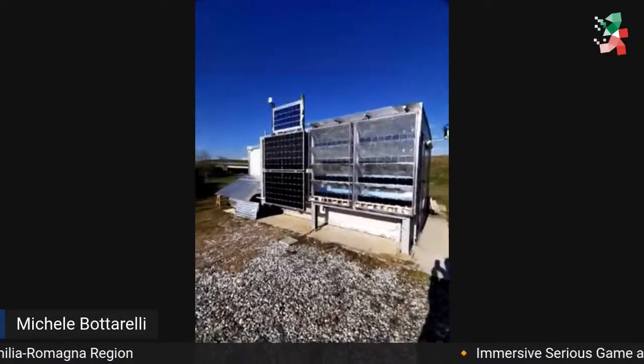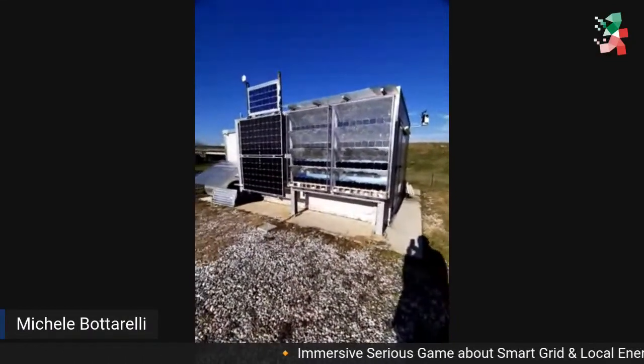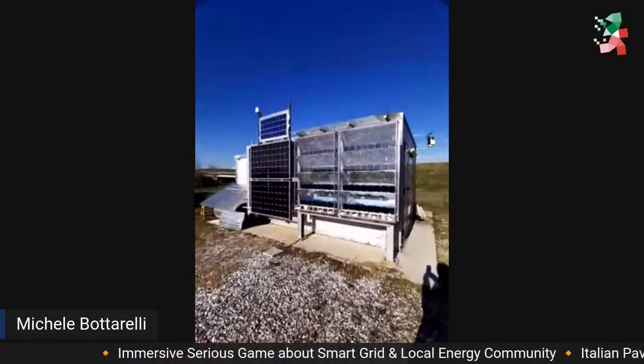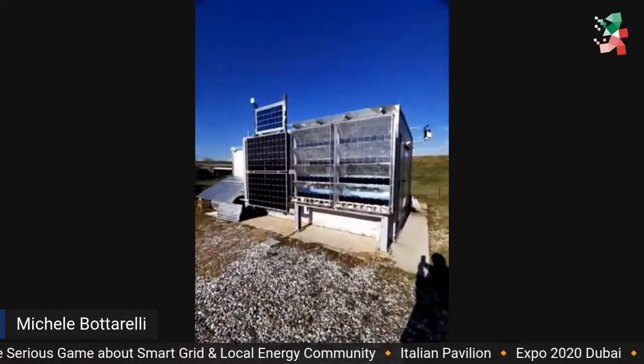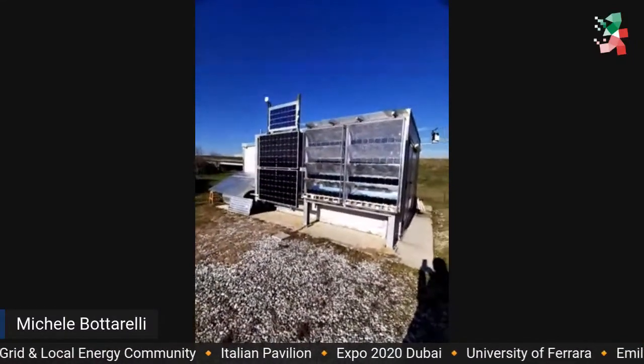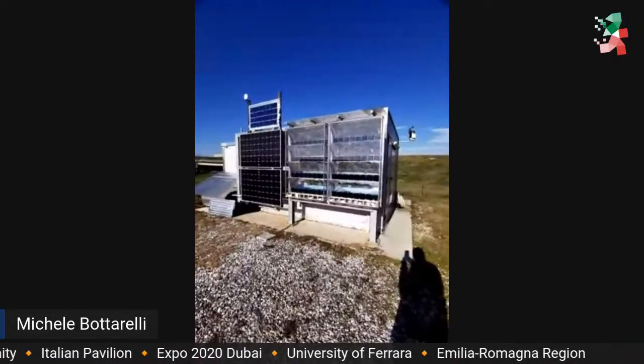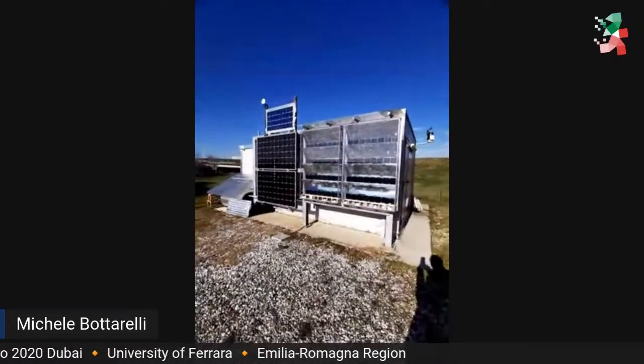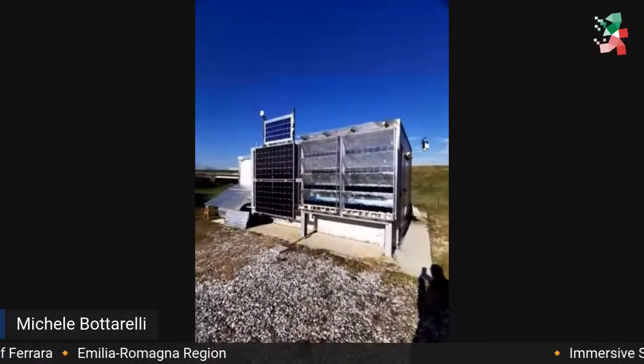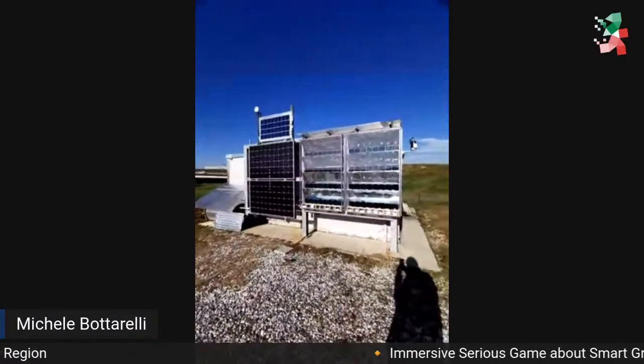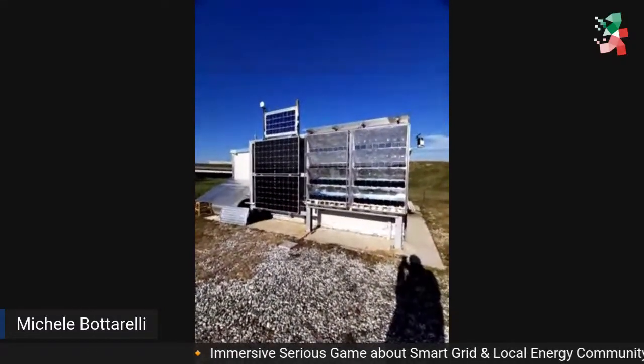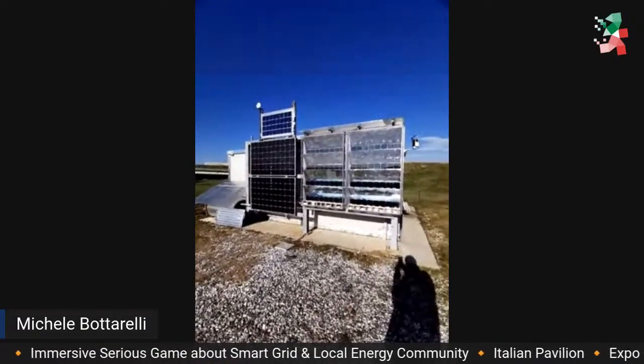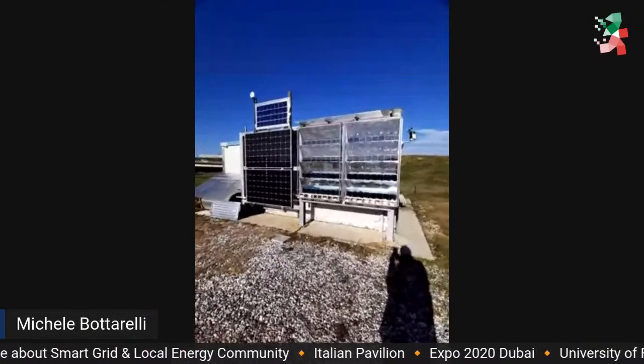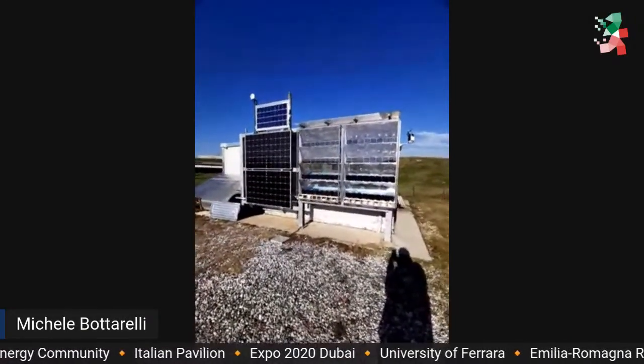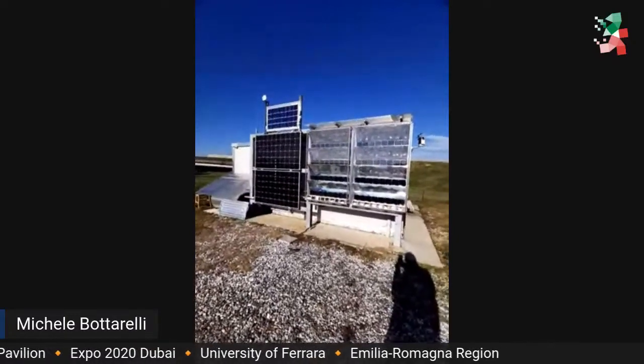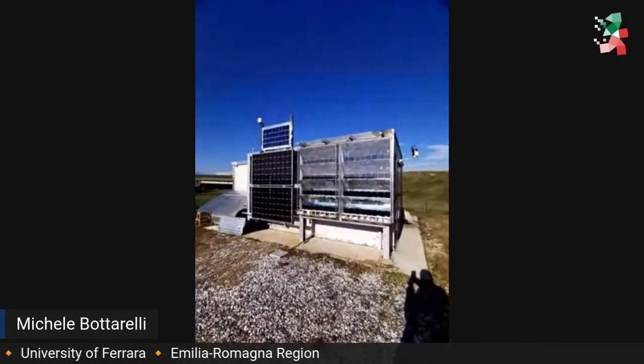This project started in 2019, and we had several problems due to COVID issues. But in any case, we were able to achieve a coefficient of performance of the heat pump around 5.5 to 6. This is only the small plant, because at the moment we have installed a larger plant directly at the university, where the heat pump is around 30 kilowatts instead of 5. But it's very similar. So this is a first prototype of the whole system.